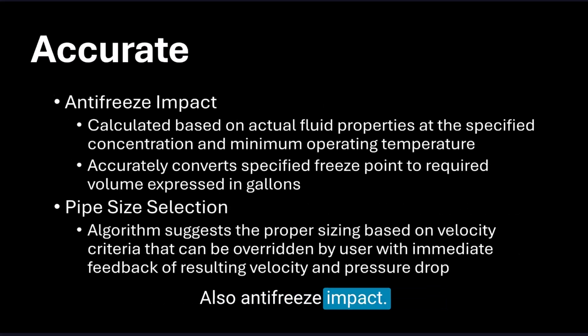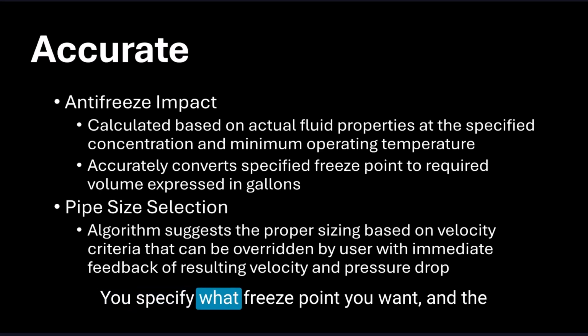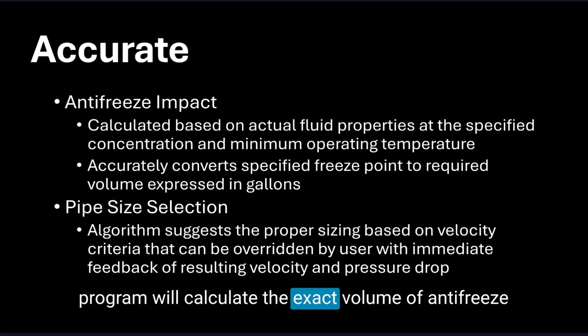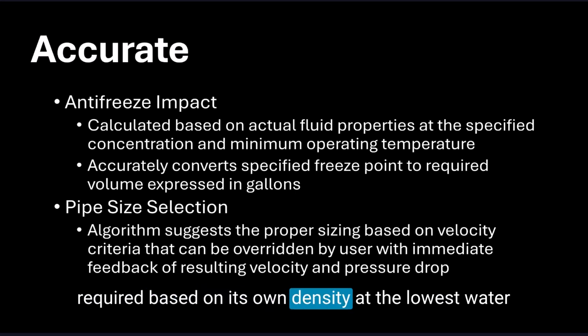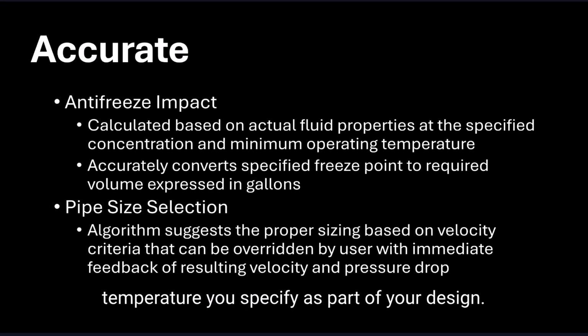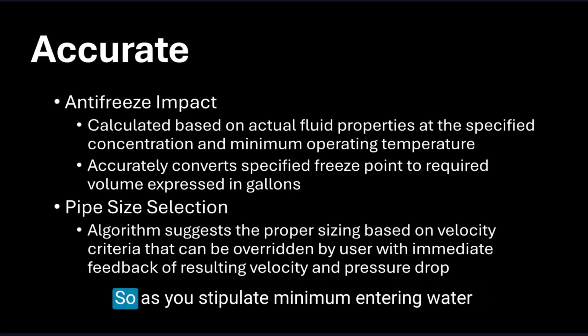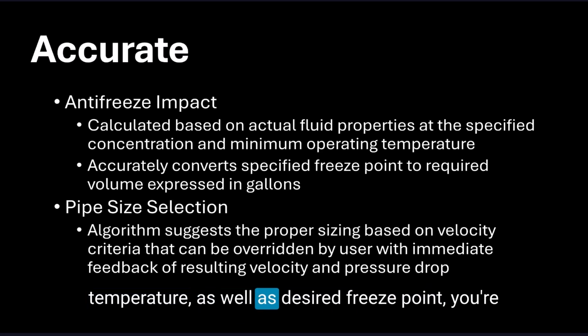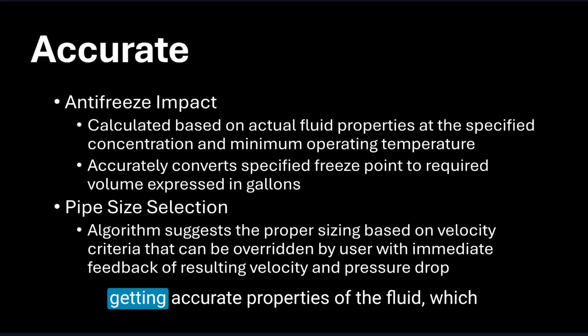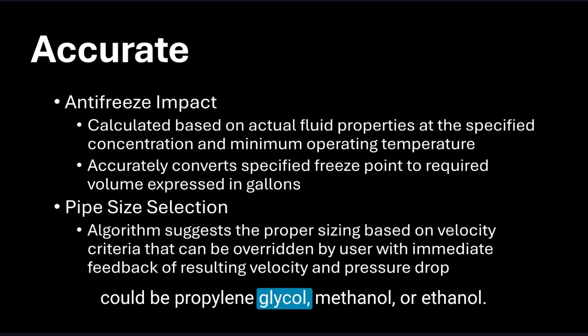Also, antifreeze impact. You specify what freeze point you want, and the program will calculate the exact volume of antifreeze required based on its own density at the lowest water temperature you specify as part of your design. So as you stipulate minimum entering water temperature as well as desired freeze point, you're getting accurate properties of the fluid, which could be propylene glycol, methanol, or ethanol.